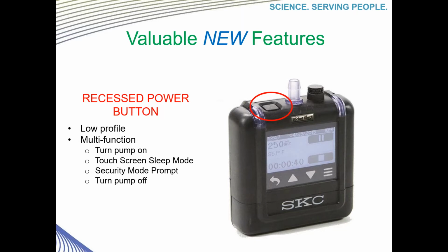It is a multi-function button that turns the pump on, but it can also put the touch screen into sleep mode and wake it up again, which prevents accidental actions while the pump is running. This button is also part of the pump's security capabilities, prompting the user to enter a password when pressed if programmed to do so. We'll touch on that more later. It also turns the pump off when you are done, but only as long as the pump is not in run mode.